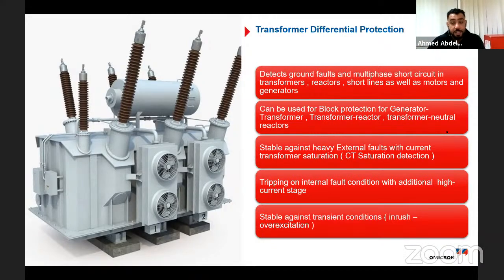And in case of CT saturation, which you will hear about frequently when you are dealing with differential protection, it might happen that the current signal coming from the CT which is saturated is not equal to the current coming from the CT which is not saturated, and this can lead to a misoperation of the differential protection. We have a way to overcome this. Yes, we have. We will talk about it in the operating characteristic of the differential protection.